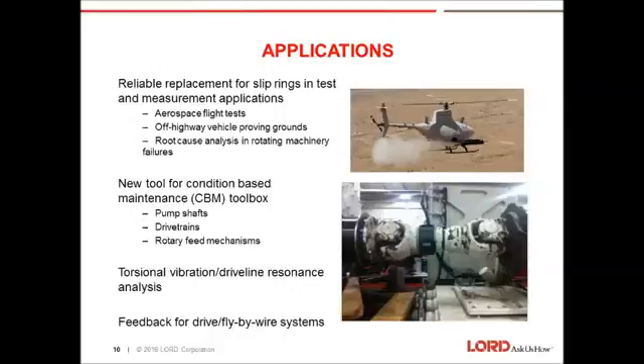Additionally, Lord believes that torque links can be used as a new tool for condition-based maintenance. So currently, lots of industrial facilities use accelerometers and thermocouples to measure bearing vibration, pump vibration, machinery vibration in general, and temperature to diagnose failures and help plan maintenance cycles. Measuring torque output from pumps and machines and motors could also be a good way to increase the accuracy and identify other problems which may not be picked up by vibration or temperature early in order to help plan the scheduled maintenance, do planned shutdowns, as opposed to losing a machine during a shift and then in some cases losing potentially $1 million an hour due to machine downtime.